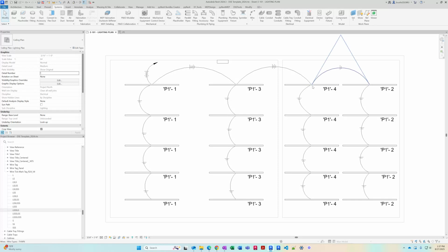That's fine. And then we come to this next piece of wire, and as you can see, circuit 2 and 4 are in the same phase group, so they should be sharing a neutral, but our wire is set up to have 2 neutrals, so it needs to be modified. Now, I indicated before you could delete this wire and you could grab something from the family. We could grab the long, short, and we could drag it across and attach it, or connect it with the wire.